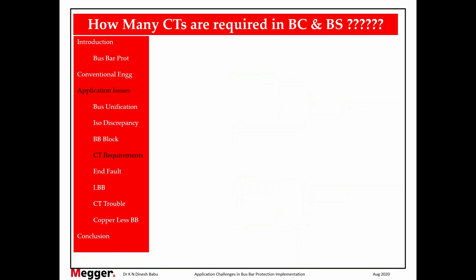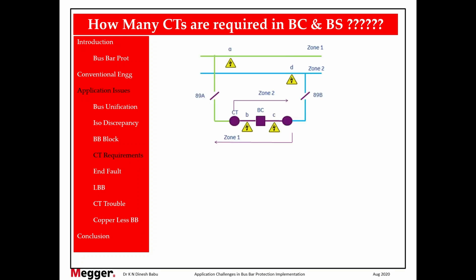Okay. How many CTs are required in bus coupler and bus section bay? One of the most commonly asked questions which comes to many people's minds. So let's discuss. An example, we have 2 buses. Zone 1, bus 1, green color. The area shown in green color is based on the zone segregation in the relay. For the relay, CT is the boundary, not the breaker. But for us, the breaker is the boundary. But for the relay, the CT is the boundary. So we have two CTs here.